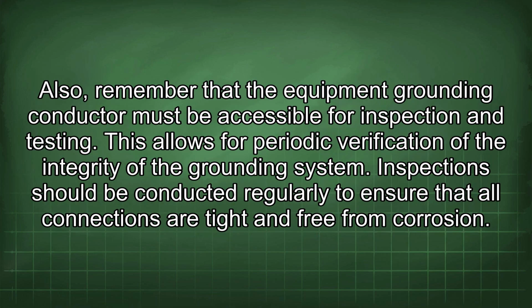Also, remember that the equipment grounding conductor must be accessible for inspection and testing. This allows for periodic verification of the integrity of the grounding system. Inspections should be conducted regularly to ensure that all connections are tight and free from corrosion.